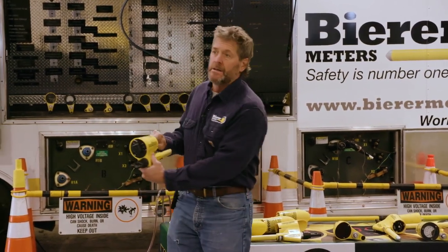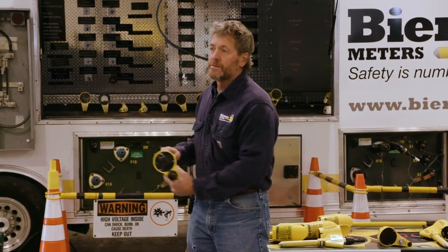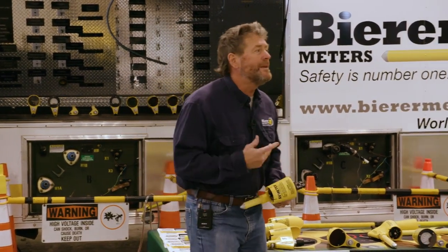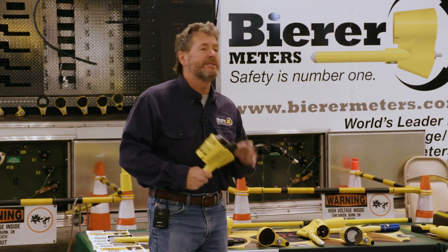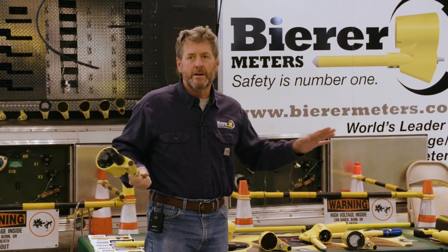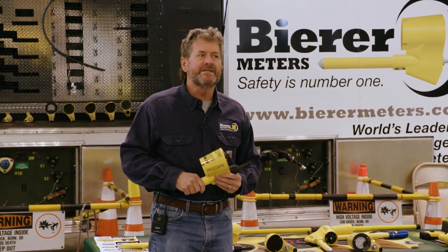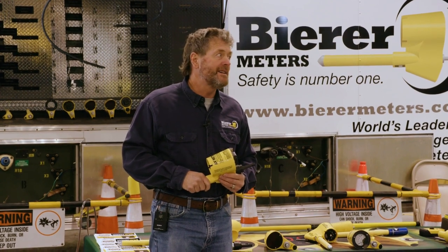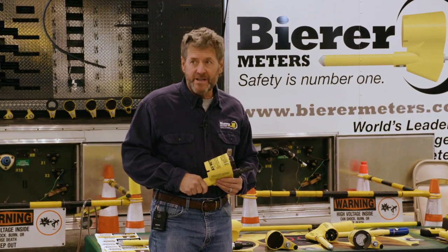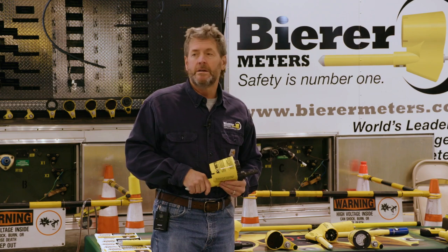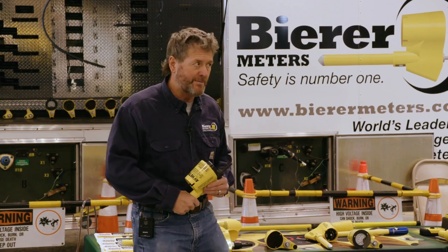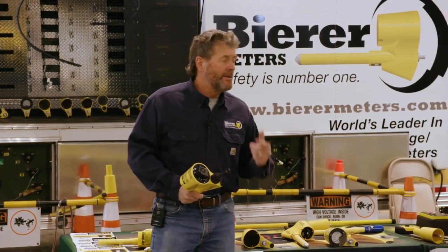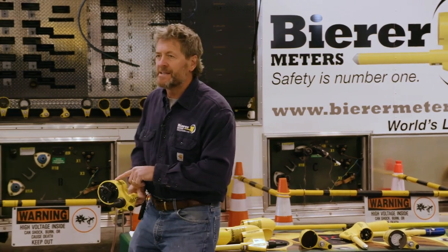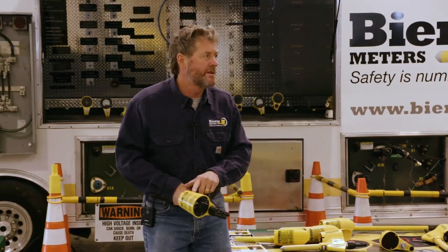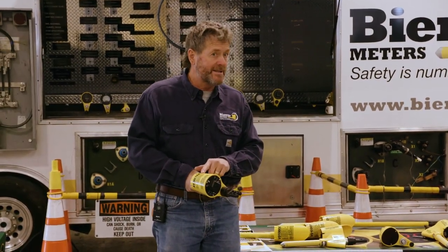Battery test, you wanna see in here, it's real simple. That only tests the battery, not the tool, anybody's tool, on a live known voltage source. It just tests the 9-volt battery. It doesn't verify your tool is functioning properly at all. It just lets you know the battery is functioning properly and it's good. There is no transformer in here stepping up 9 volts to high voltage for a true tool functionality test.